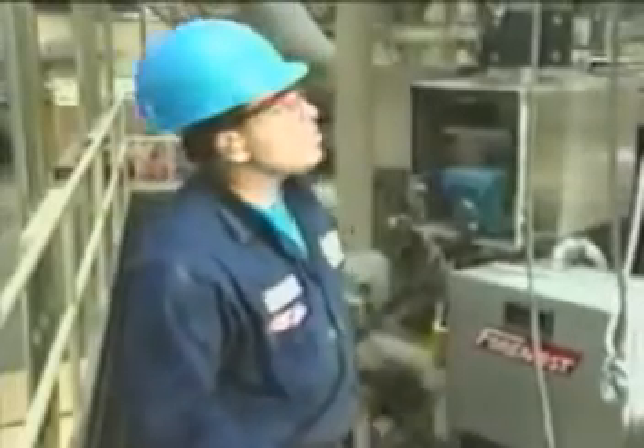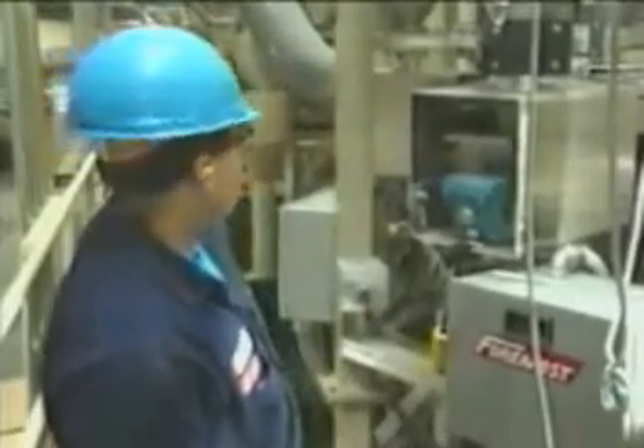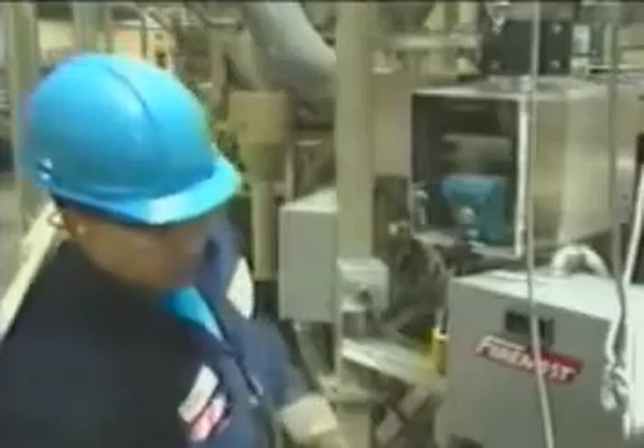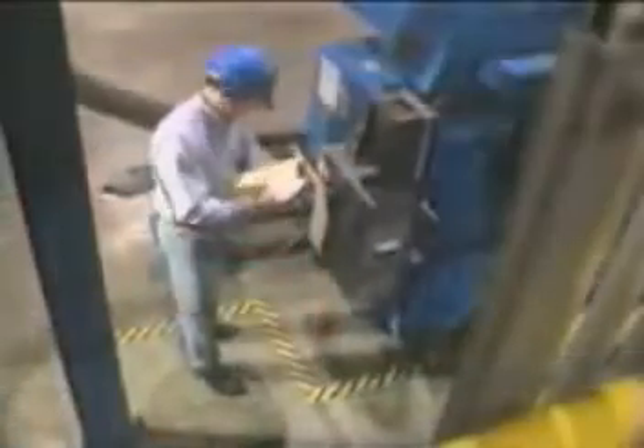Once you've completed the work, be sure the equipment is operationally intact and the tools and other non-essential items are cleared. Next, notify all affected employees that locks and tags will soon be removed. Perhaps by counting employees, you can be sure that everyone is clear from the area. Then remove lockout and tagout devices. Each worker removes his or her own lock. Remember, it is illegal to remove someone else's lock. Tag should be signed and turned in.